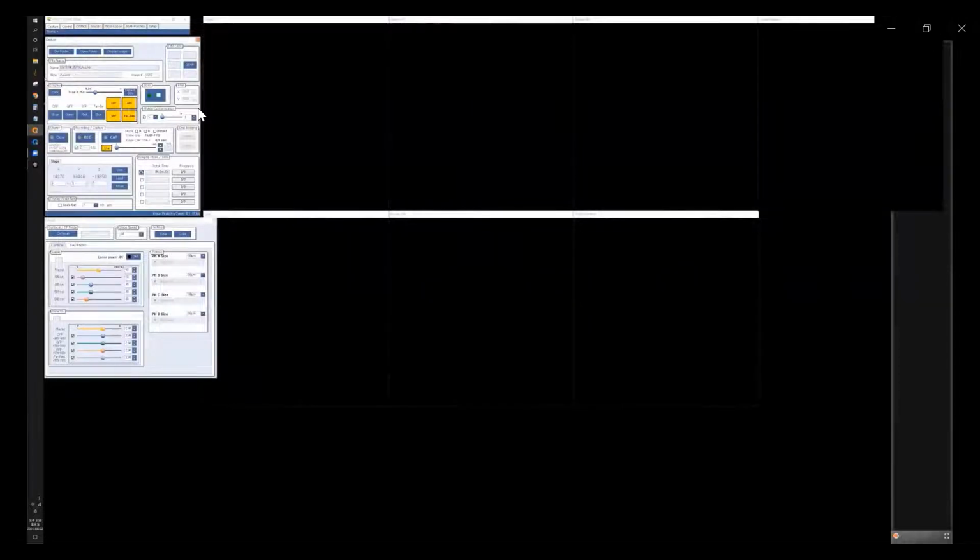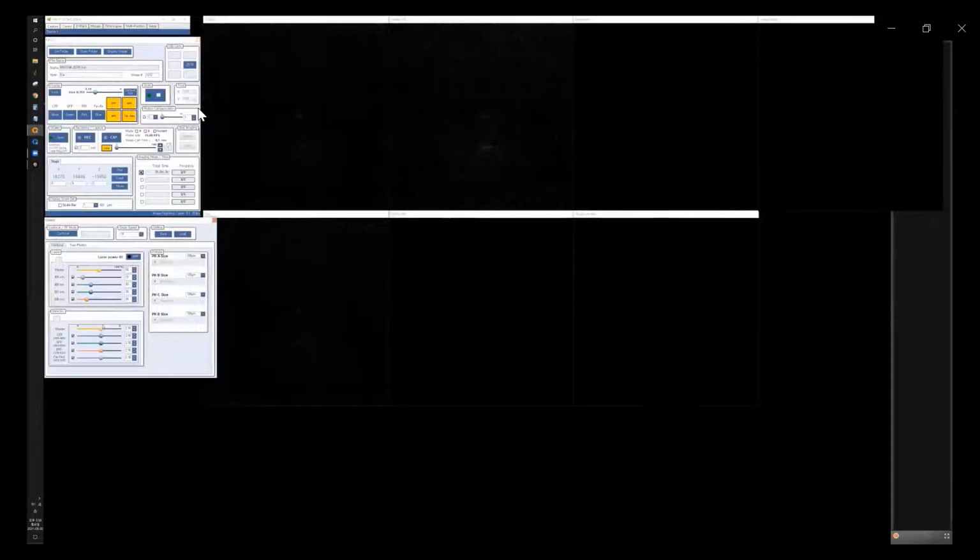For setting the directory to save the acquired data, click Set Folder and set the directory. In the note, we can set the file name to be created following the numbering. Then turn the shutter on for initiating the excitation. Then lower the stage in the Z-axis using the stage controller until we find the focal signal.